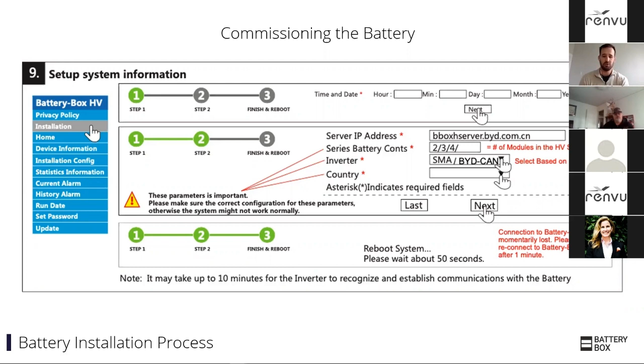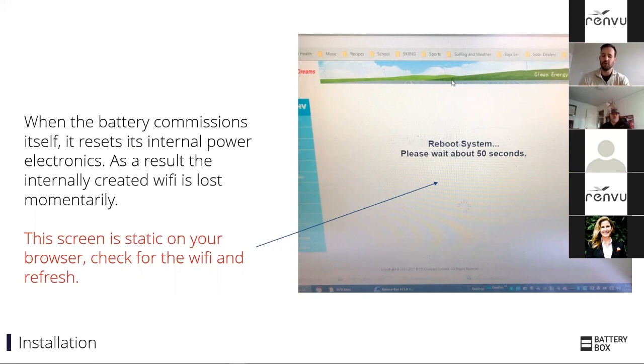One little watch-it that trips some people up: when you're logged in here and you commission the system, it actually reboots itself. And since it's internally created Wi-Fi, when it reboots, you actually lose that Wi-Fi connection. So one thing that can trip up new users is they might stare at the screen waiting for it to refresh. In reality, it's done - the commissioning process is finished. You just need to refresh the web page. It's just that the Wi-Fi connection's been lost, so you're looking at a dead web page.